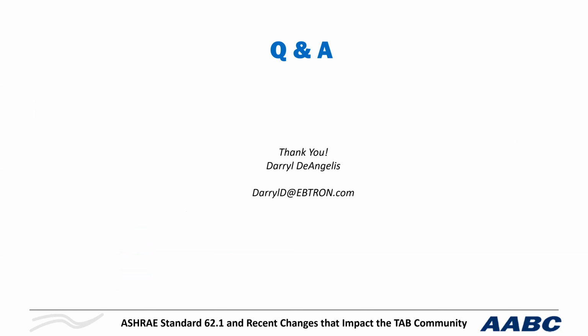So the first question here is, why are exhaust rates in Table 6-2 listed in terms of flow rate per area rather than air changes per hour? That's a good question. Air changes per hour is a challenging thing because it requires knowing the volume of the space, and the volume of the space is not set. It's easier to calculate the area of the space. A lot of the ventilation rates, and sometimes the exhaust rates, are also listed per occupant. For example, the number of toilets you have is based on the occupancy as well. I hope that answers the question.